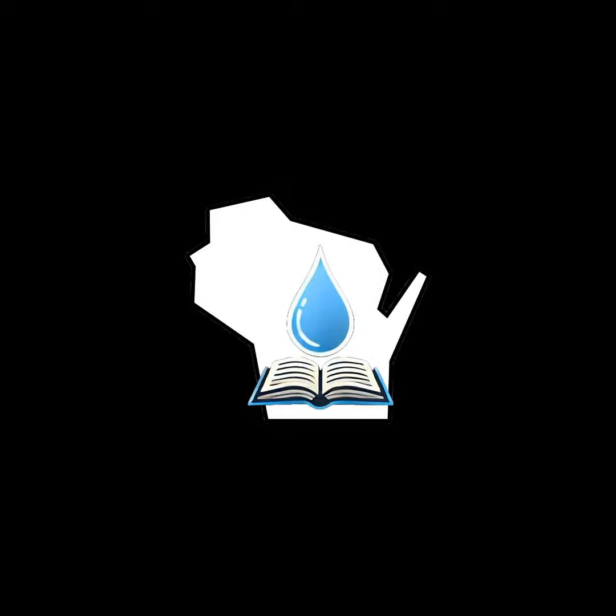Number 5, a return vent, also known as an island vent or loop vent. Wisconsin calls it a return vent. Number 6 is a circuit vent. This can be used with wall outlet fixtures, it's just not as common. Usually you see the circuit vent applied to floor outlet fixtures. Number 7 is the combination drain and vent laboratory sink system. Only legal for laboratory sinks.